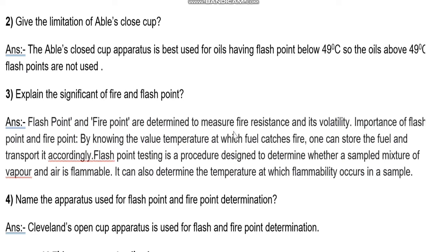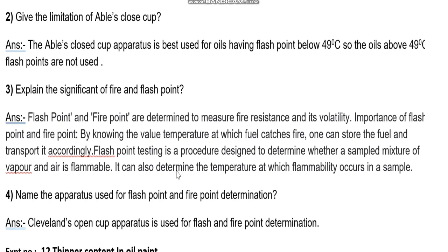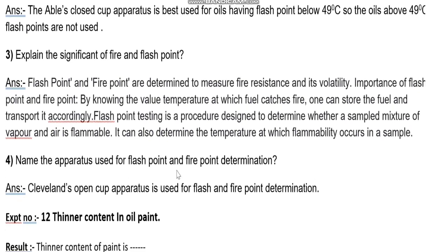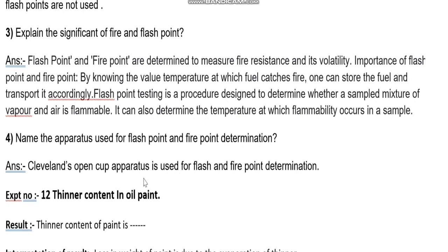Significance of flash and fire point: flash point and fire point are determined to measure fire resistance and volatility. By knowing the temperature at which fuel catches fire, one can store and transport the fuel accordingly. Flash point testing is a procedure to determine whether a sample mix of vapor and air is flammable and the temperature at which flammability occurs. Cleveland's open cup apparatus is used for flash point and fire point determination.